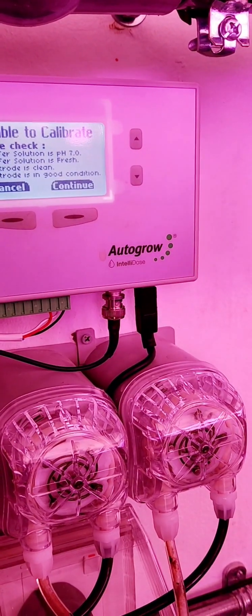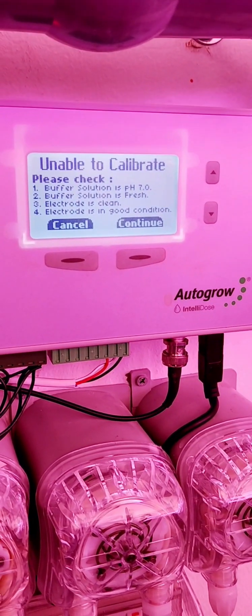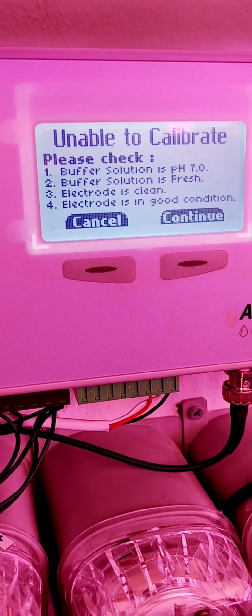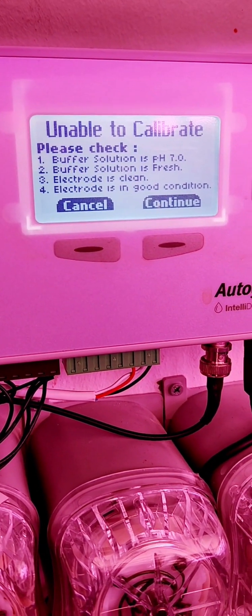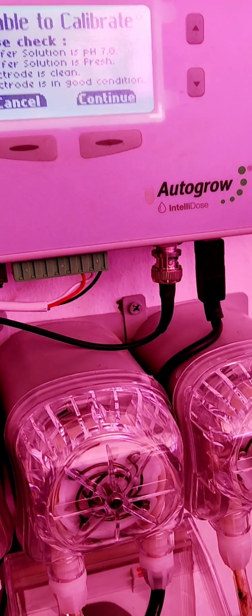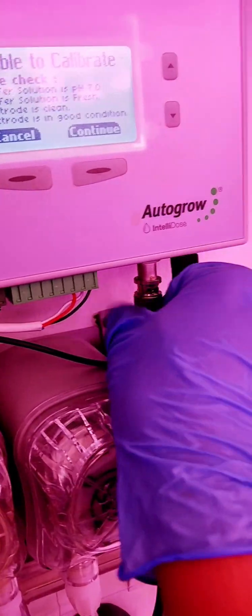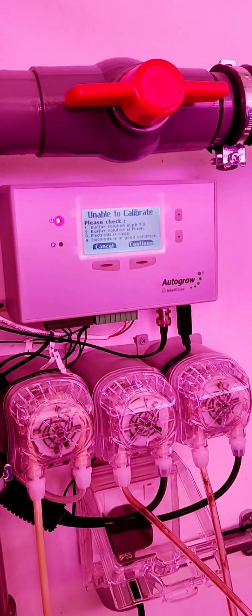Because all the rest of the probes that I have calibrated, only this probe that I got issued. This is how we can. This is one way how to identify. The sensor is defective. Or is something maybe you have to fix in the system. Or I even plug it out. Here. I disconnected. But it's still the same. Nothing changed. I prefer to inform the supplier to come and check on this. If not, really need to change the pH sensor. That's it. Thank you.